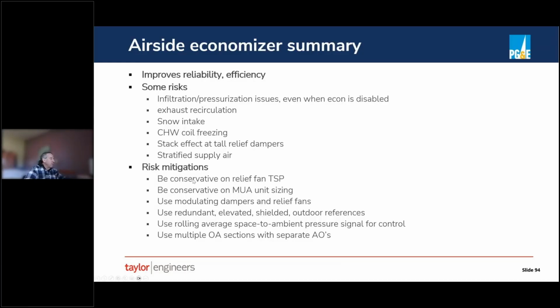So one of the things we've seen is to basically be conservative on the relief fan total static pressure. It doesn't cost you much to design your relief fan for 1 inch of external static compared to 1/2 inch or 1/4 inch. Be conservative on makeup unit sizing. So if you're using chill water or some other system where you're going to be shutting off your economizer, as I said, you can have infiltration issues. And so you need to have some sort of way to keep the space pressurized even when your economizer is off. Use modulating dampers and relief fans. We've seen data centers where they try to use stages, and stages just simply don't give you good control. So you want to make sure you have fully analog control.